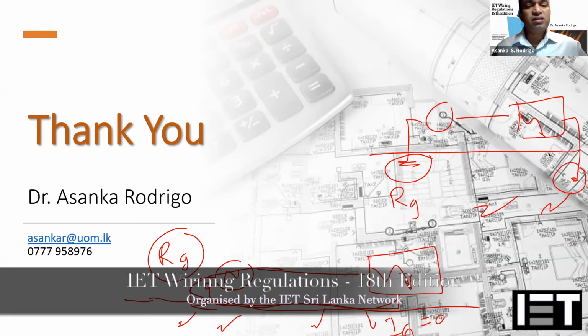As I said, there is no such requirement. I have to explain it in a little detail because of the time limitation. I'm advising you that in the IET wiring regulations, there is an appendix for voltage disturbances. In there, there are different types of earthing arrangement for MV/LV systems, like with the substation, whether you have a transformer body earth separate and the neutral earth separate, and then combine them together, combining with the impedance. Likewise, for all those options, what the earthing requirements and insulation requirements are is in the separate appendix of the IET wiring regulations under voltage disturbances.